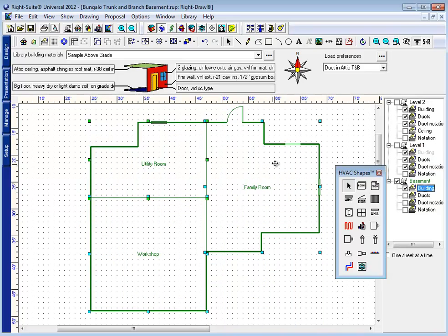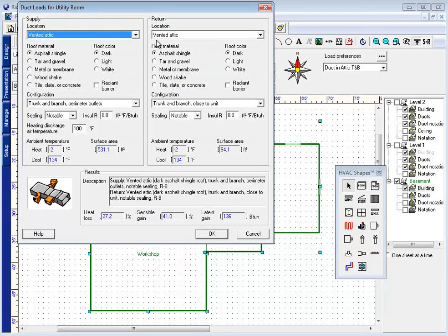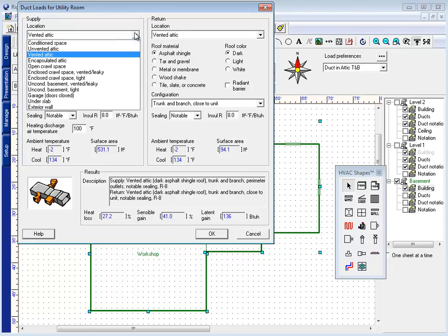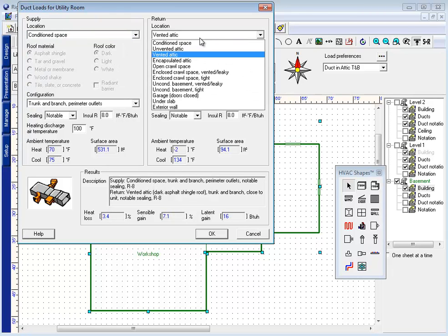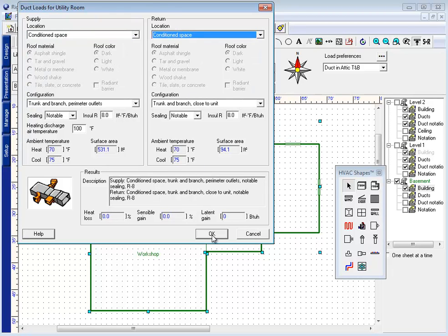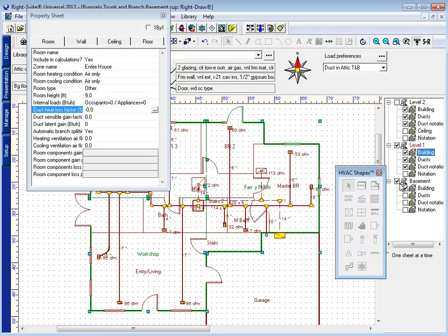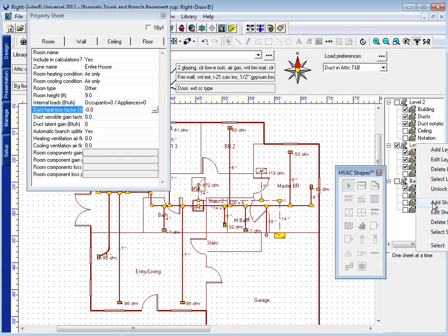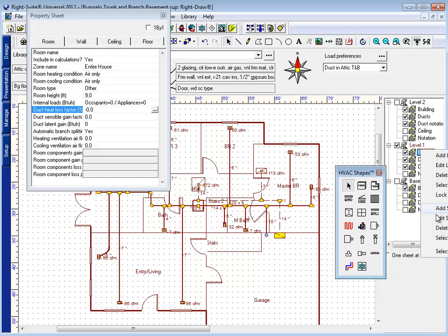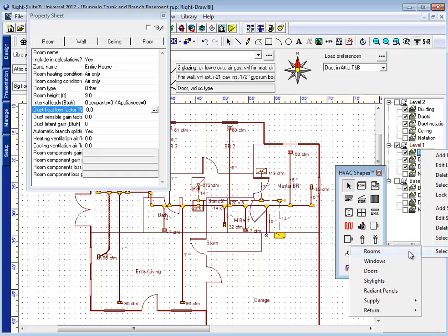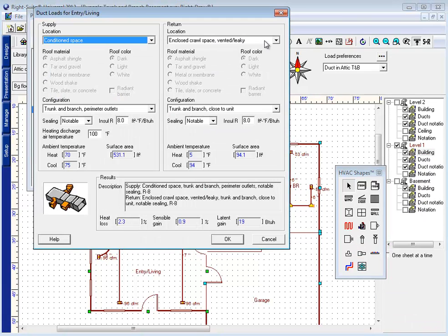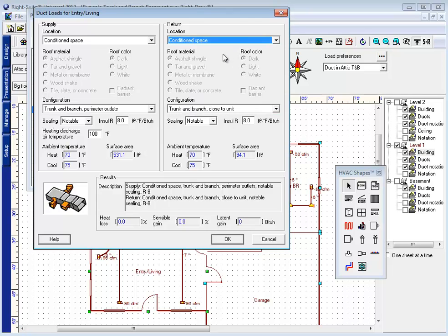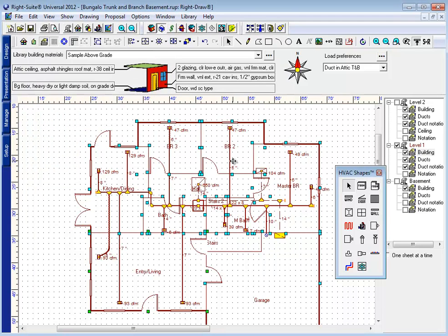The first thing I want to do is make sure that my duct load is correct. Since the location of my duct system is going to be different, I want to make sure my rooms are calculating their duct system in a conditioned space. That's on the room tab of the room property sheet, and I'm going to want to check this for both my level 1 and my basement and change the location of my duct system to conditioned space. This is going to take the duct load for these areas down to zero.